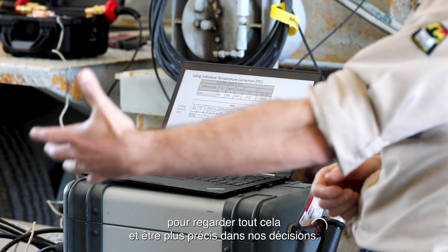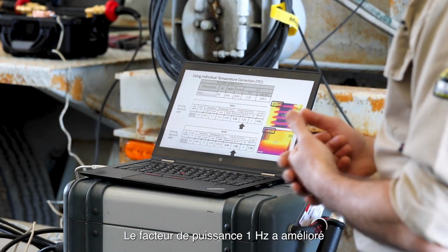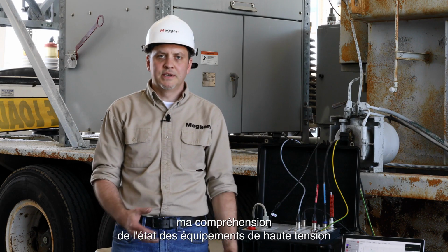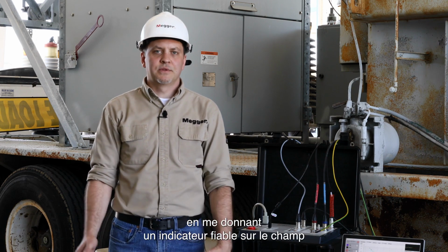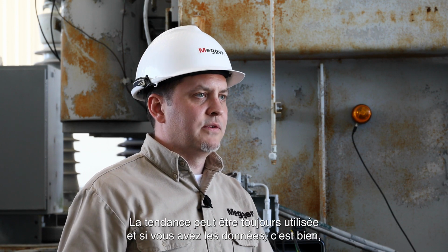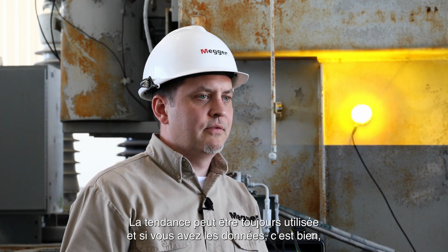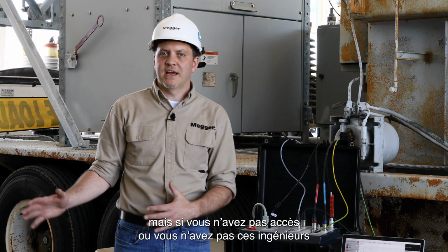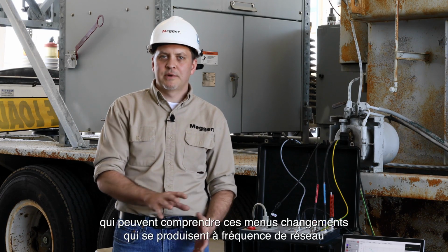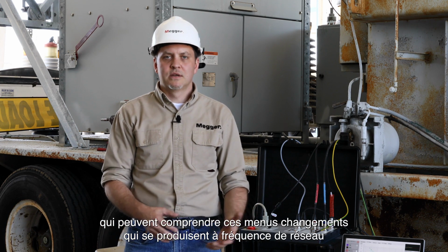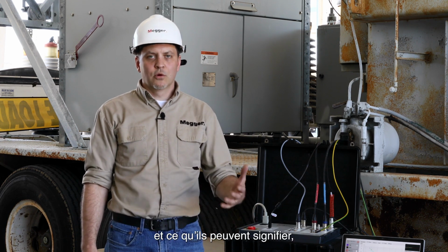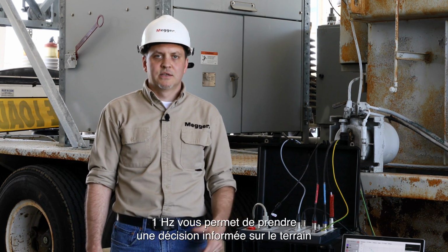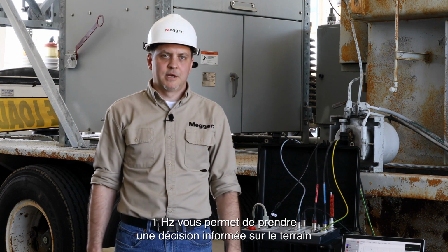1 Hz power factor has improved my understanding of high voltage asset health by giving me a reliable indicator in the field without the need for trending. Trending can still be used, and if you have the data, it's great. But if you don't have access or you don't have those engineers who can understand those minute changes that happen at line frequency and what they may mean, 1 Hz allows you to make an informed decision on the spot so that way you can have an improved maintenance plan.